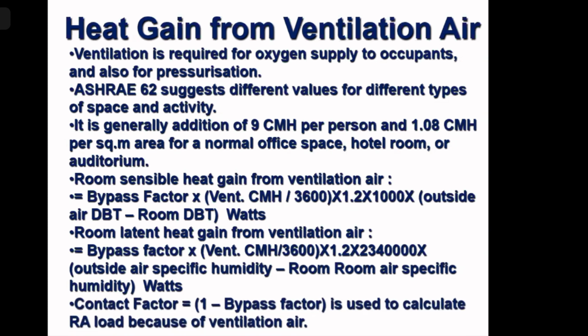Next. Contact factor is 1 minus 0.12, so 0.88. So use contact factor in place of bypass factor to calculate the balance amount of heat that is going to the return air. Same formula, but use contact factor in place of bypass factor to get the balance amount of heat that will be going into the return air as sensible heat and as latent heat. Next.